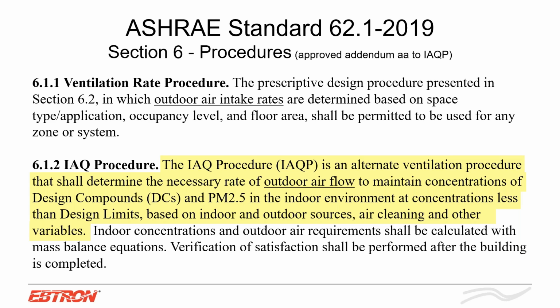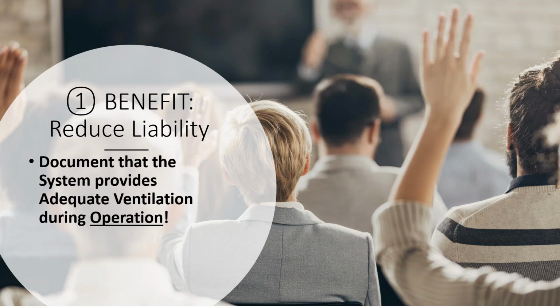A thing to note about this though, since you are downsizing your air handling units, you have to verify and basically have a report that shows, hey, these contaminants have been removed before the building is occupied. So that's something to note if you ever need to bring in more outside air and you don't design your system to accommodate for that, right? Those are the two procedures that are really the driving forces in the industry.